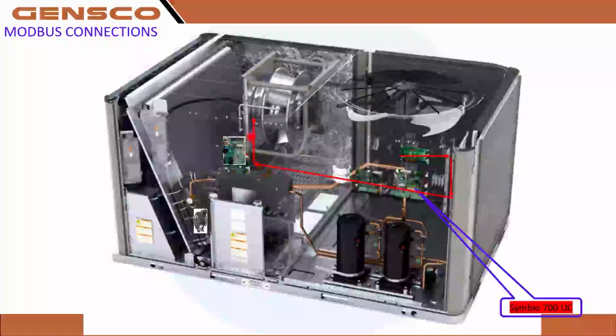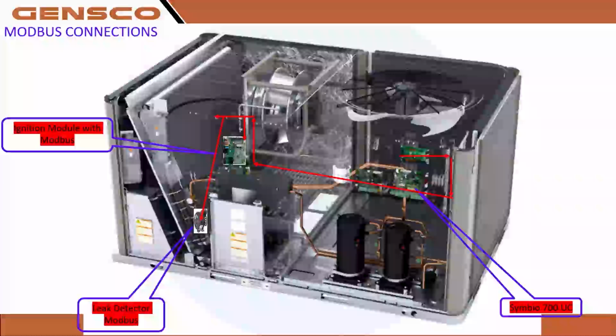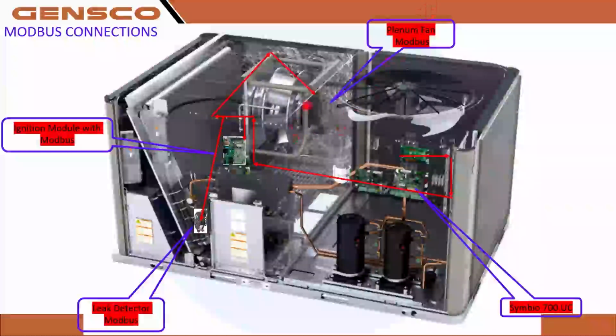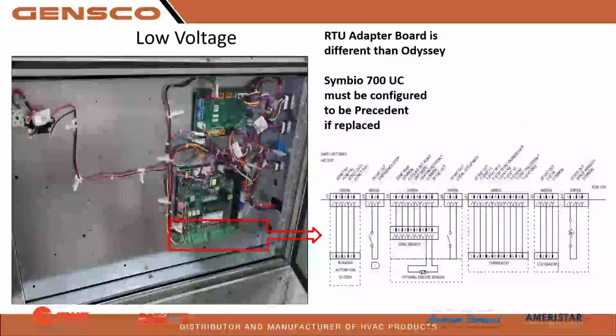And we're following the path of Modbus. It ties into your leak detection. Again, on the 12.5 and above, we will have another leak detection Modbus connection on top of the evaporator coil. And then it carries through to the plenum fan. So that's a nice little routing. I mean, it's not an actual picture, but if we have to get into diagnostics, this is a great one that I send out, saying, okay, let's follow some wires. Low voltage. So this is that low voltage panel, and here's that hinge connections right here.